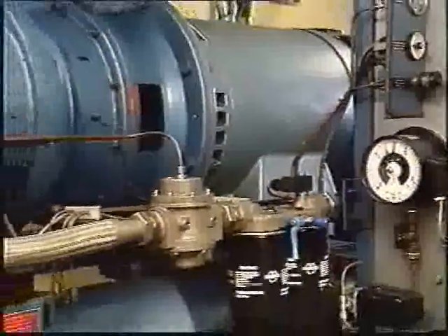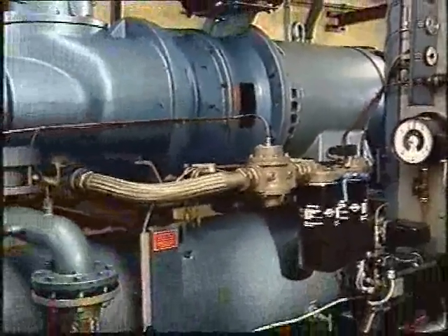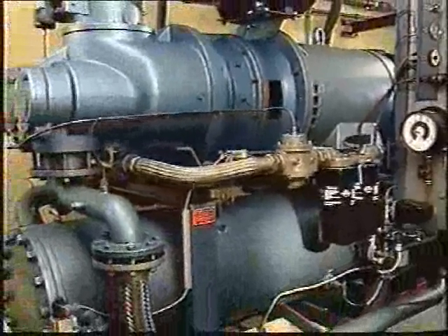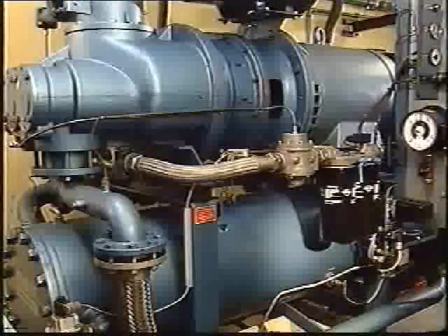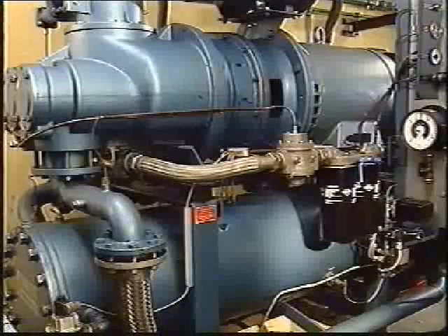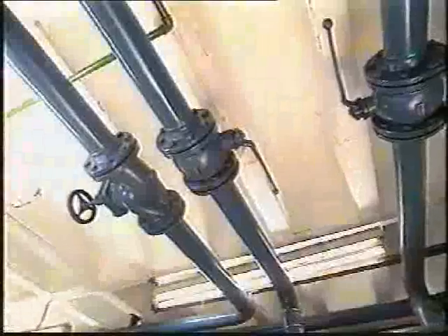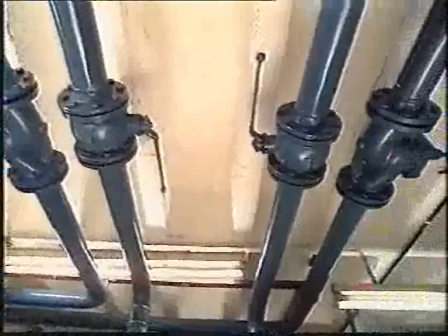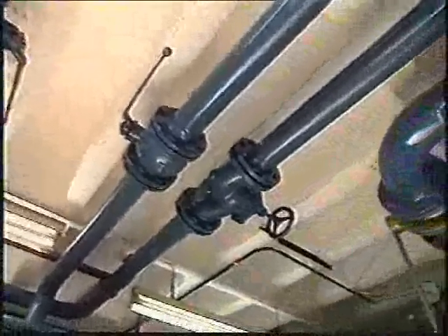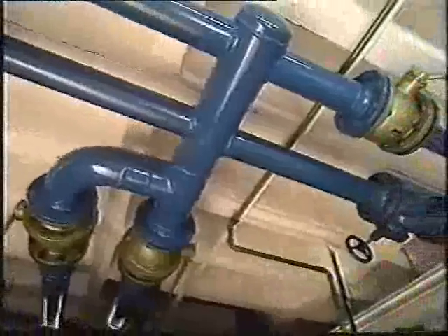When designing and installing a compressed air system, the distribution of the air has a major effect on system performance. The size and layout of the pipes is critical for economical operation of the system. The design should also allow for future increases in demand because modifications can become very expensive.